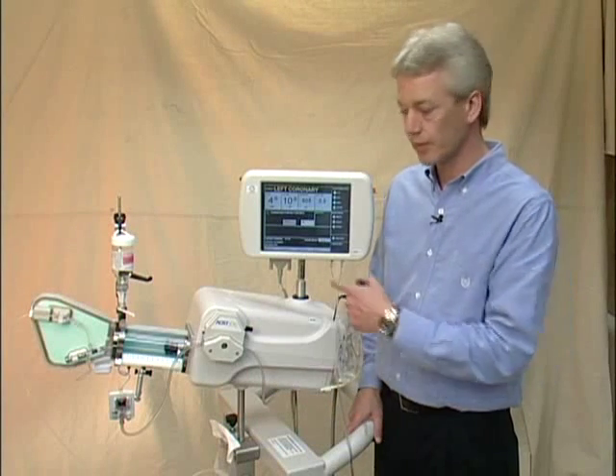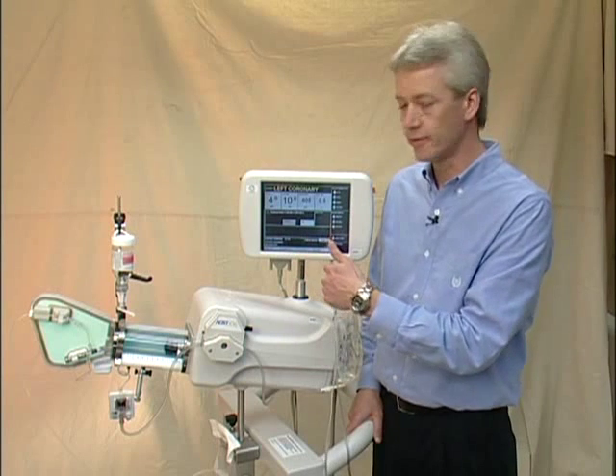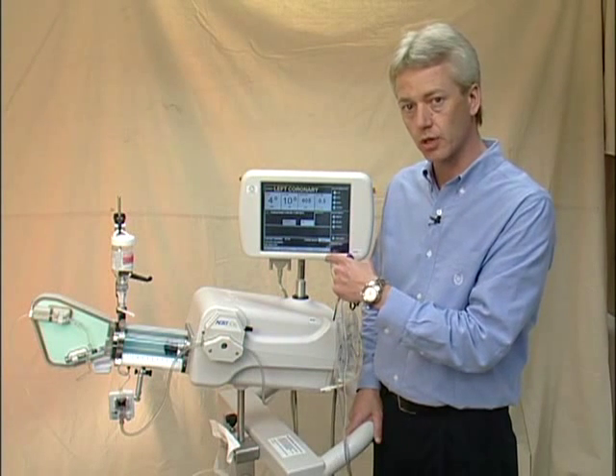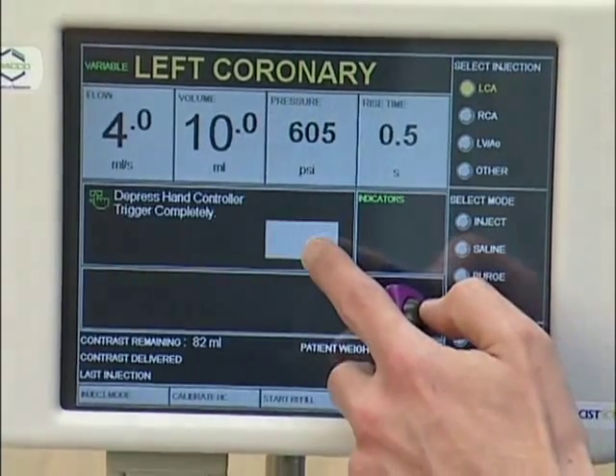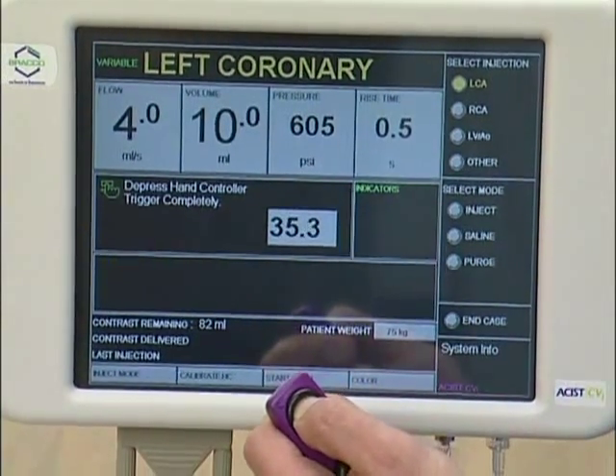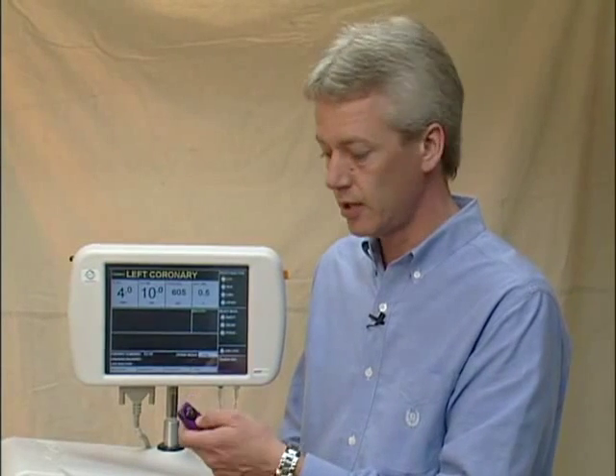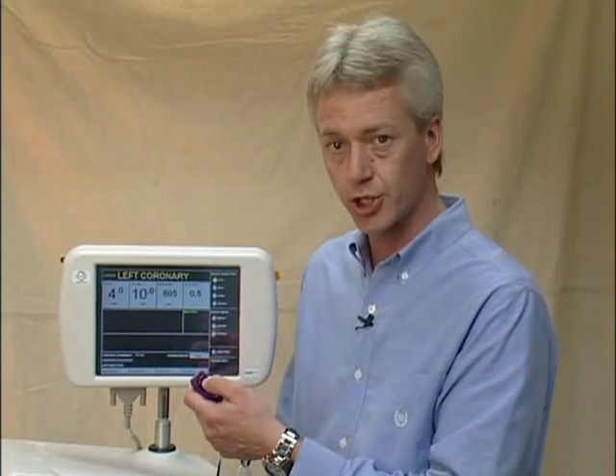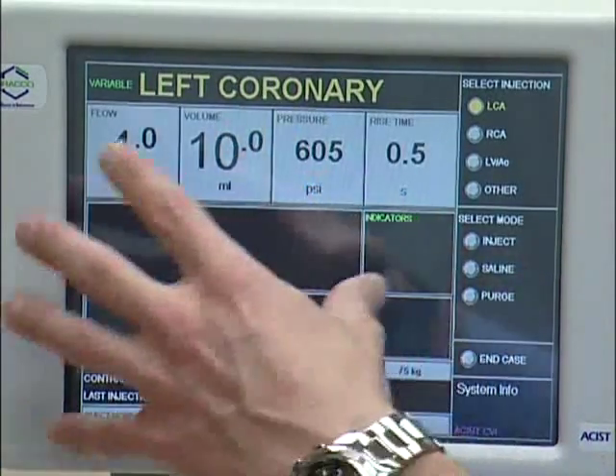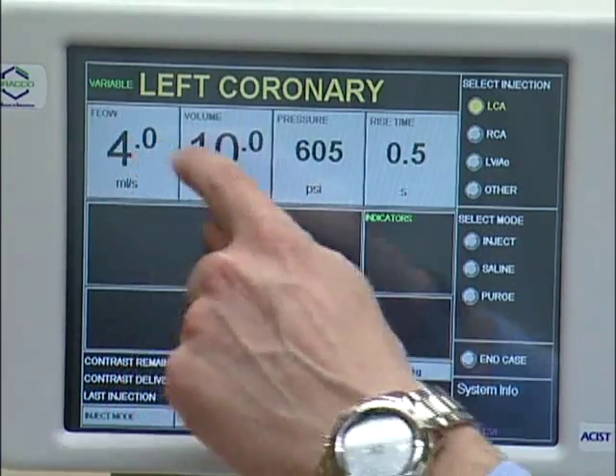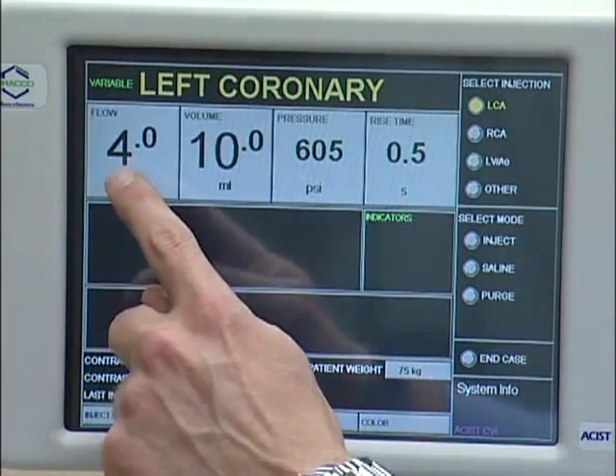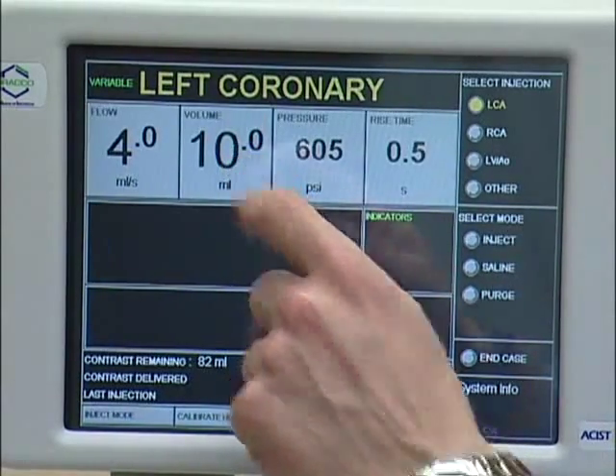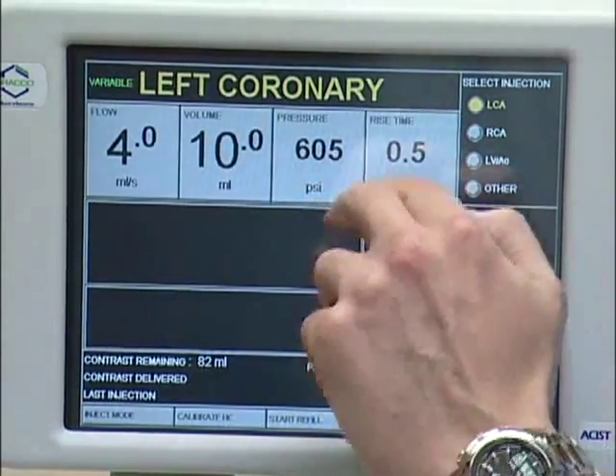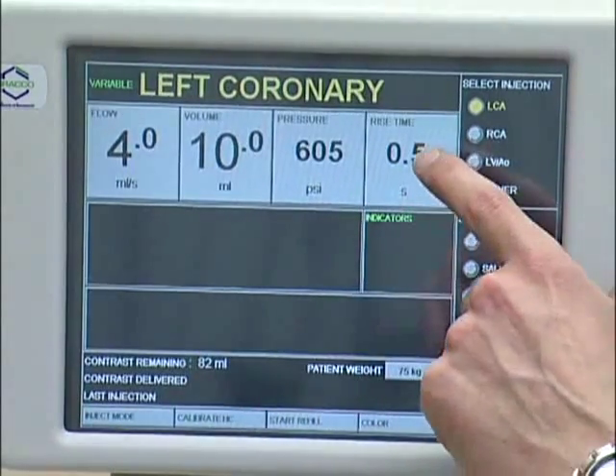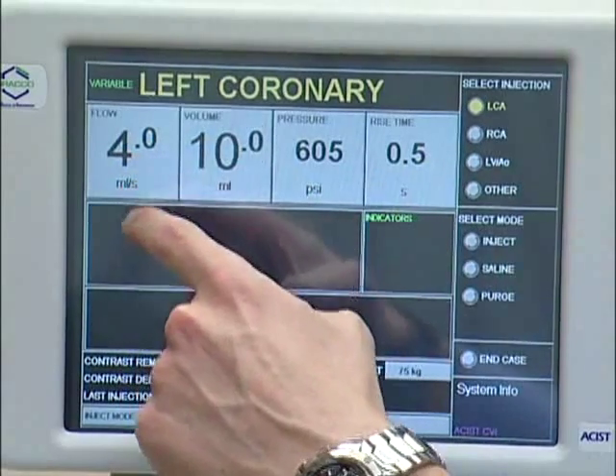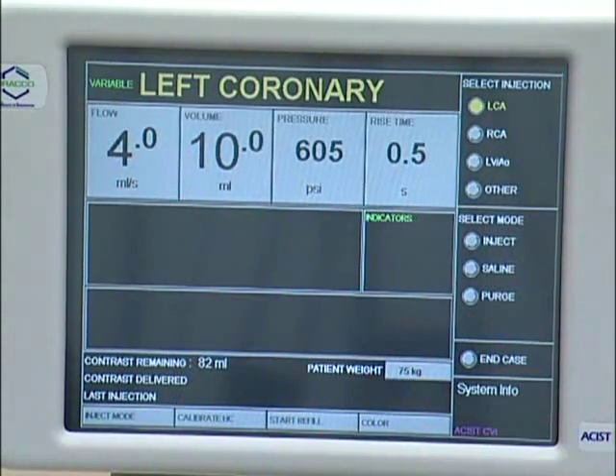Once the setup is complete, we'll come to what we call the main screen. The first operation for the operator on the main screen is to calibrate the hand controller. This is done by pressing OK on the screen and giving a full depression on the top button of the hand controller. Once the hand controller has been calibrated, it's now calibrated to that physician's touch. Now let's review the touch screen and the functions of the screen. On the top we have our parameters. We have our flow rate, which is how fast, our volume, which is how much, our pressure, which is our limit for the syringe pressure, and our rise time, which is the amount of time it takes to get to this flow rate with a complete depression of the hand controller.